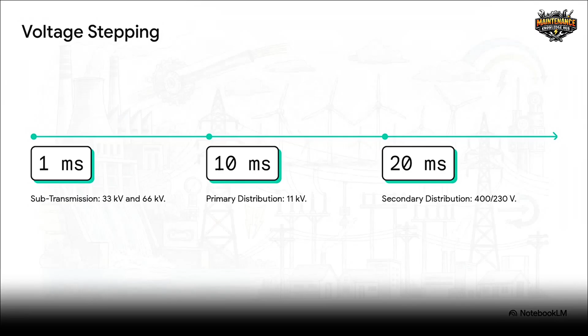This is the high-speed interstate highway for our traveling power, allowing it to cross hundreds of miles with very minimal transmission losses. That brings us to Section 3, stepping down the power in the sub-transmission phase. As the electricity exits that highway, it goes into the sub-transmission system. Here, at regional grid substations, the voltage is reduced to common levels, like 33 or 66 kilovolts, so it can be distributed to different industrial areas.